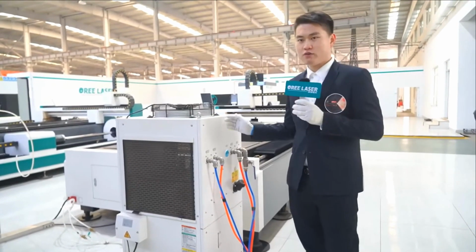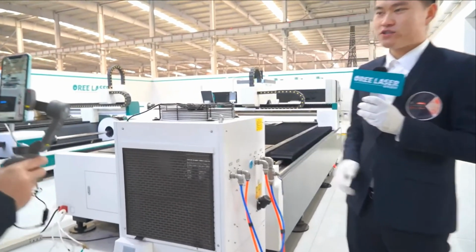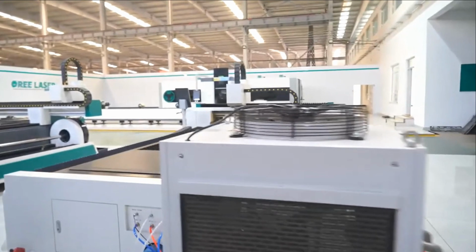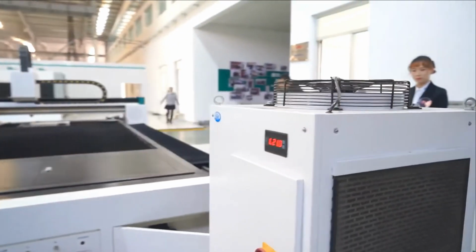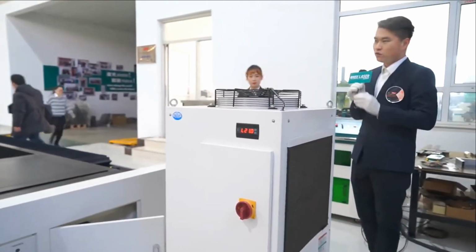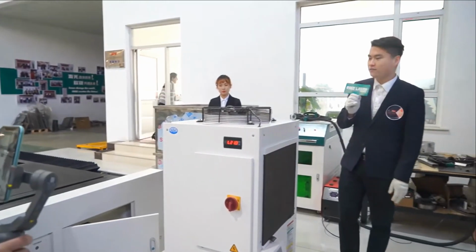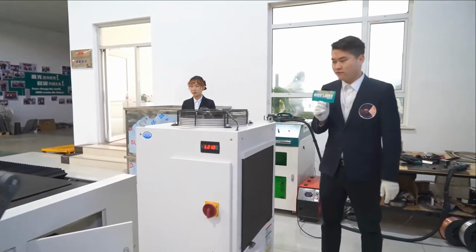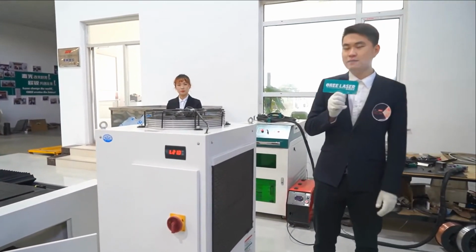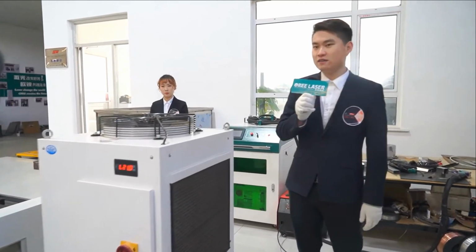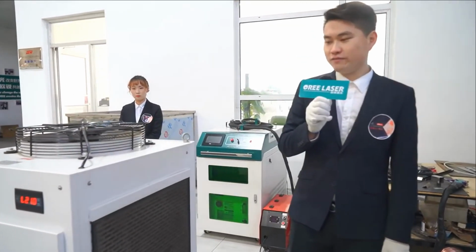It is dual temperature and dual control, with 2 water channels to cool 2 positions respectively: the laser source and the laser head. Low temperature cools the laser source, high temperature cools the laser head. The fast cooling speed keeps both always in the best working condition.